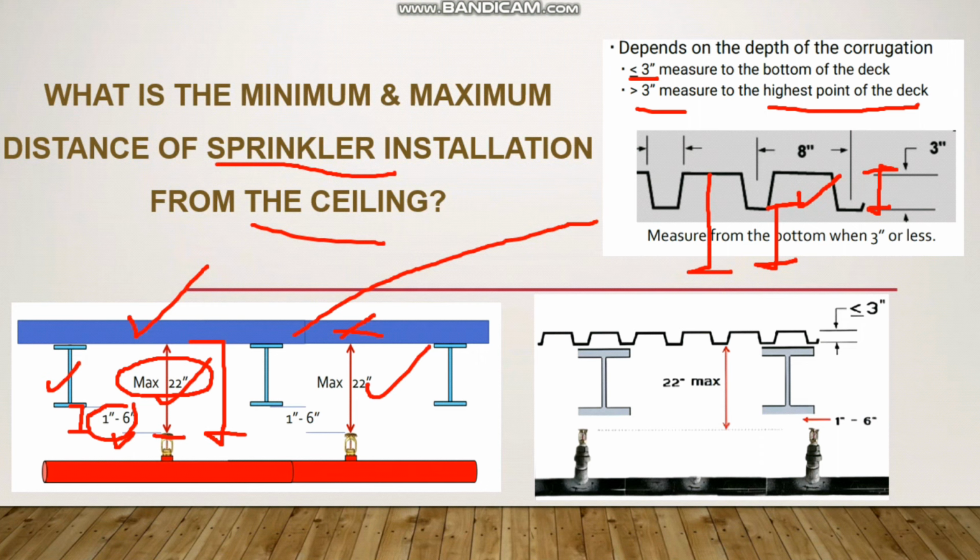So you can see here this is less than 3 inch. So that is the reason I measured from the bottom of this roof to the top of the deflector. It should be maximum 22 inch. Okay.